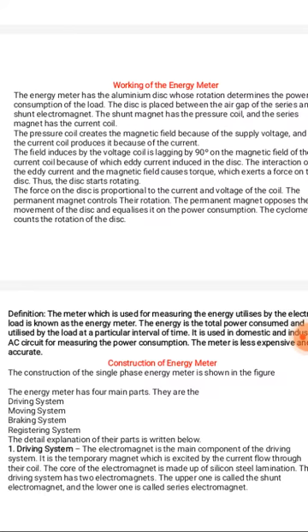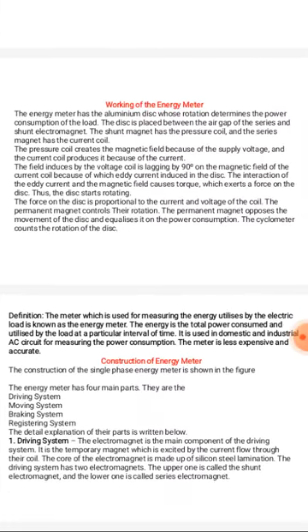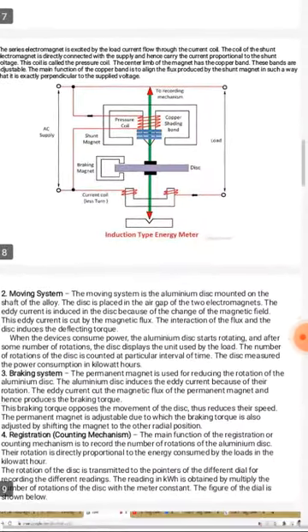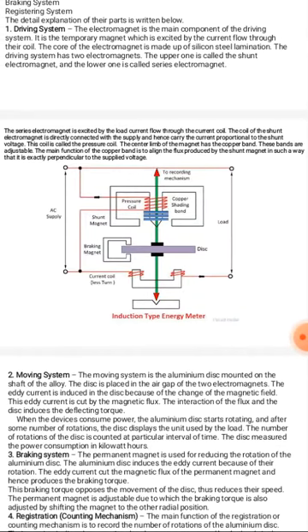The force from the disc is proportional to the current and voltage of the coil. The permanent magnet controls the rotation. The permanent magnet opposes the movement of the disc, that is called brake magnet, and it opposes due to Lenz law which equalizes it on the power consumption. The cyclometer counts the rotation of the disc. Here register mechanism counts the number of rotations or number of impulses by this meter.